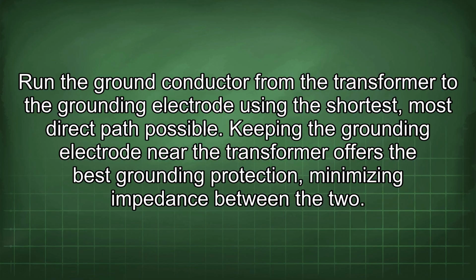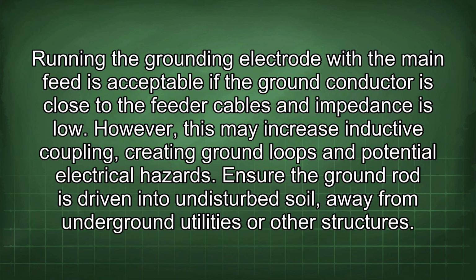Keeping the grounding electrode near the transformer offers the best grounding protection, minimizing impedance between the two. Running the grounding electrode with the main feed is acceptable if the ground conductor is close to the feeder cables and impedance is low. However, this may increase inductive coupling, creating ground loops and potential electrical hazards. Ensure the ground rod is driven into undisturbed soil, away from underground utilities or other structures.